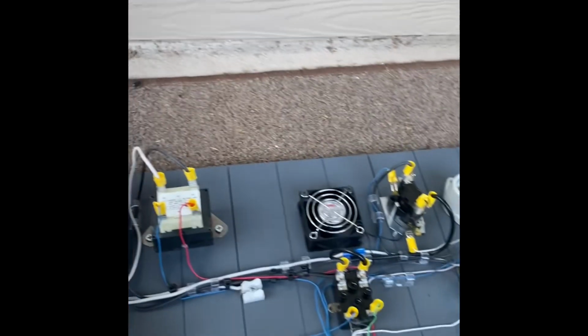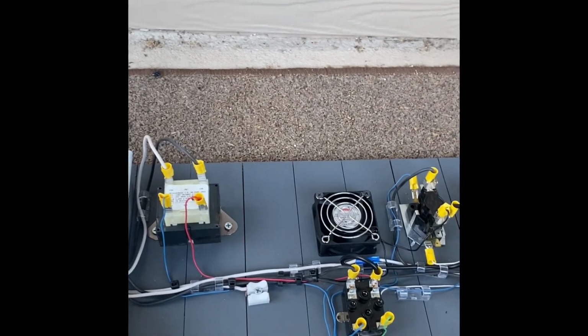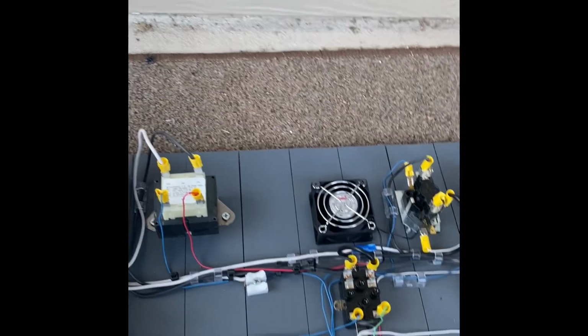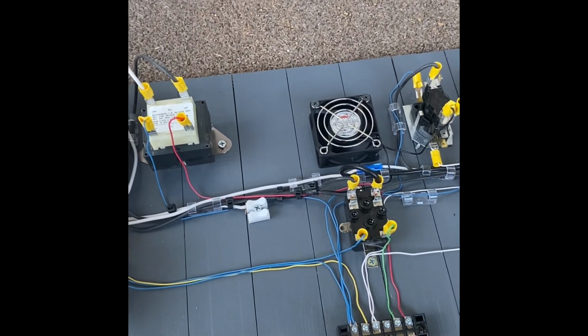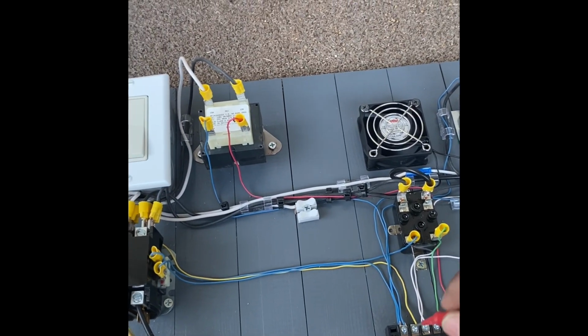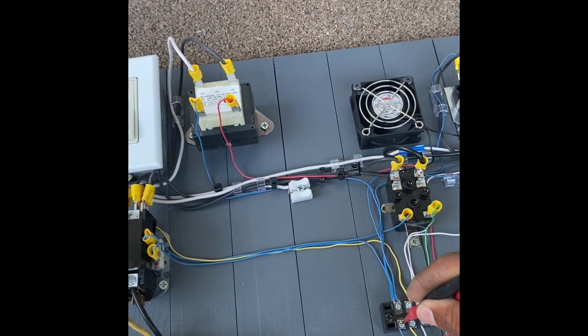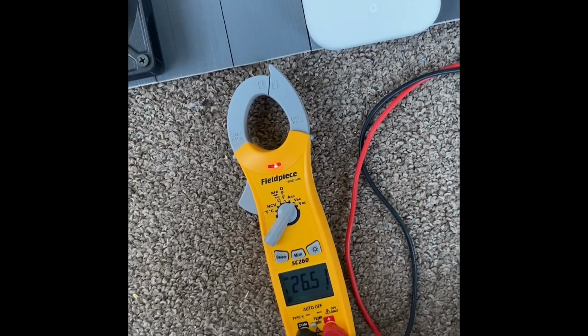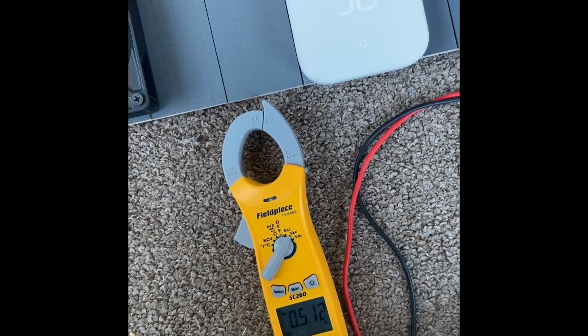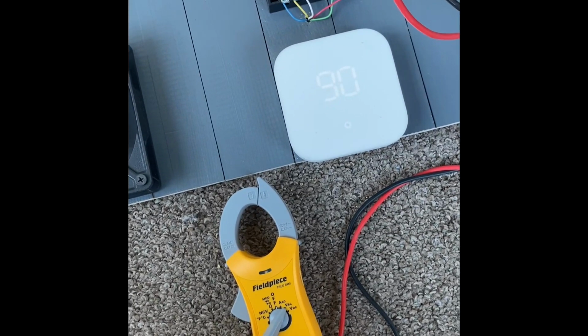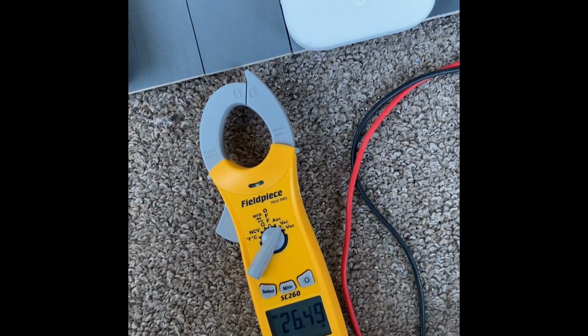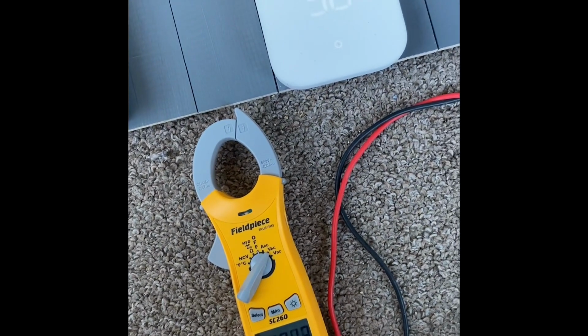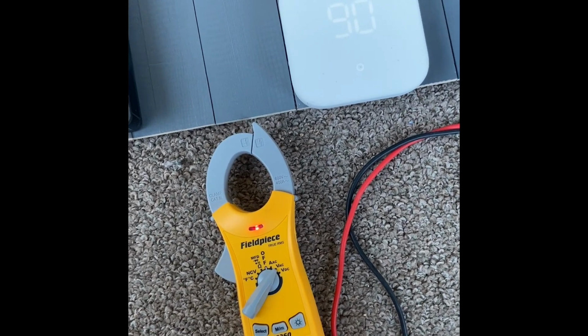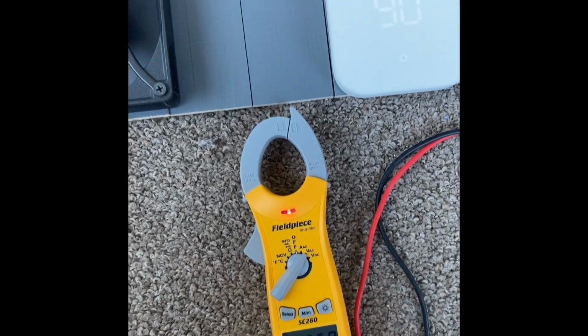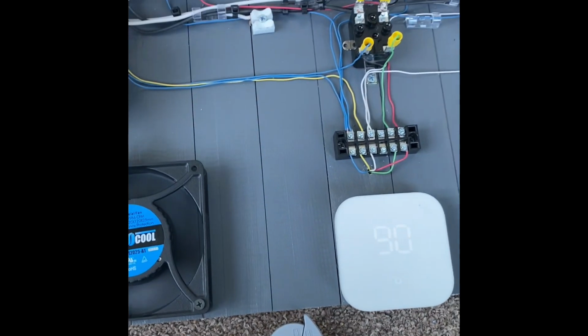Now we're gonna check power on the low voltage wires in the terminal blocks. So one side, which is R, the other side is common, and we have 26 volts. Then we've got green, which is your fan, and common, we have 26 volts. Now the unit is running on cooling, we're gonna check cooling and common, and we have 26 volts. So this unit is 100% operational right now.